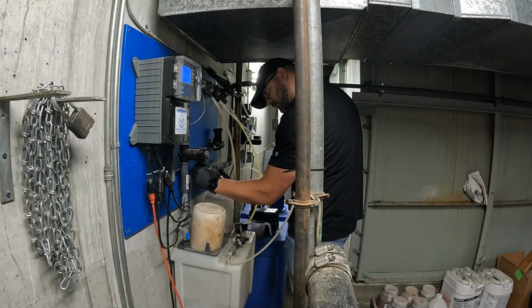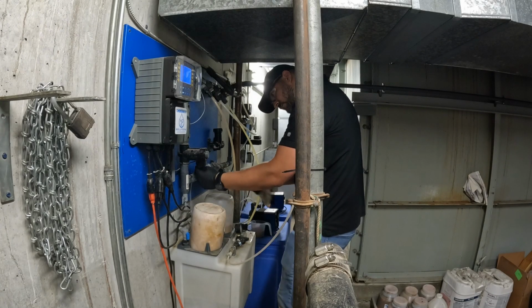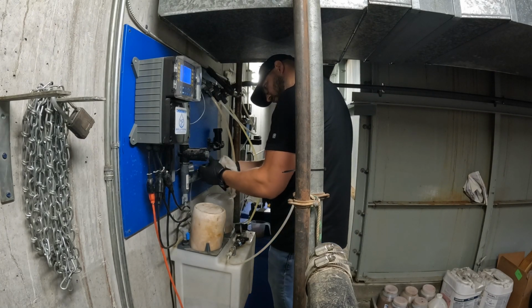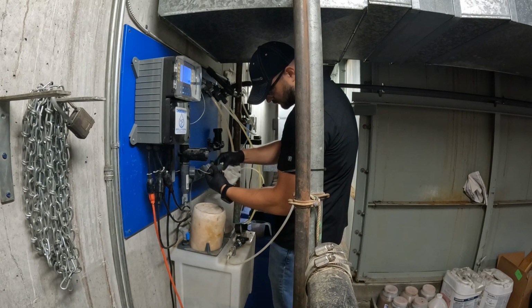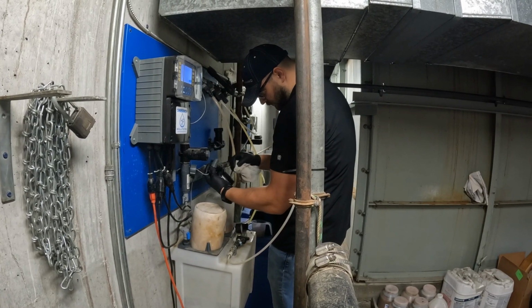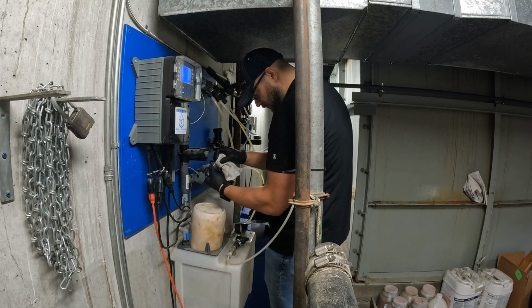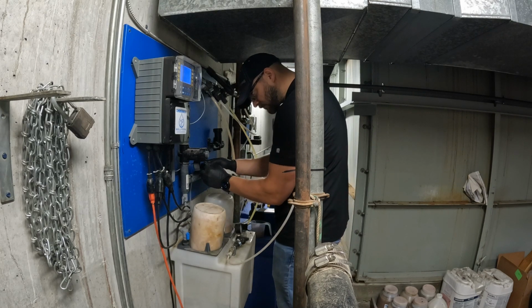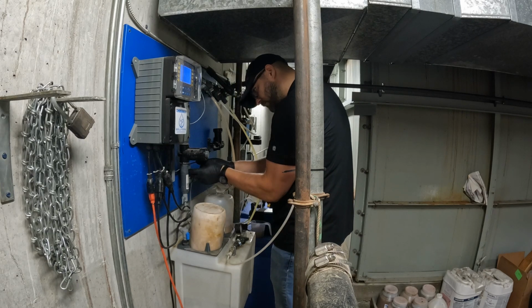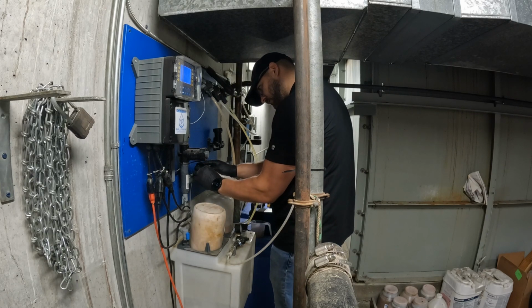Now we will move on to cleaning off the conductivity probe. It is important to use a soft cloth and wipe in a single direction when cleaning off the probe. If there is buildup that will not come off, you can use a Scotch-Brite pad or cleaning pad to remove it. Again, wiping in the same direction. Once it has been properly cleaned, you can reattach it to the manifold and move on to any other probes or sensors that are present.